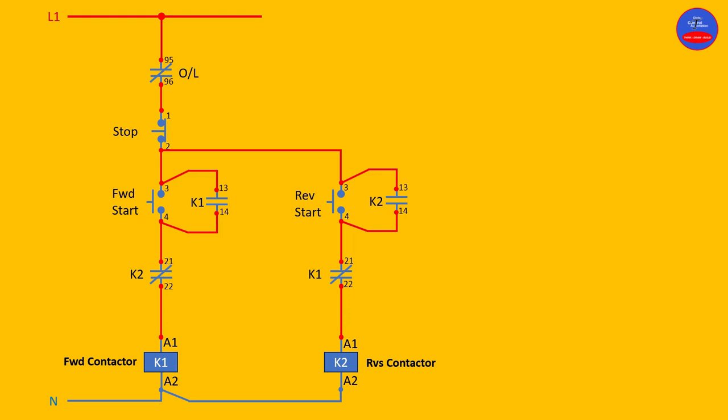We are coming to operate the circuit and see how it will behave. The overload terminals 95 and 96 are normally closed, and our stop button is normally closed, so current is flowing through 95 and 96, through the stop button. Now we are coming to operate the motor in the forward direction. Terminals 21 and 22 on the reverse contactor K2 are normally closed.